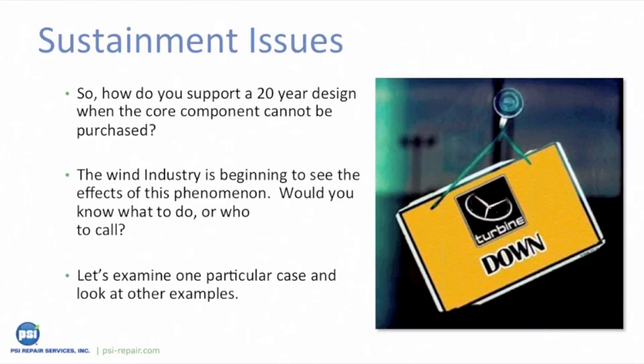The wind industry is beginning to see the effects of these factors on electronics. Failures occur in the form of printed circuit boards, line and rotor IGBTs, anemometers, encoders, drives, inverters, pitch controls, and generator controls — some of which are in short supply or simply no longer available, and they're failing too frequently to keep up with demand.